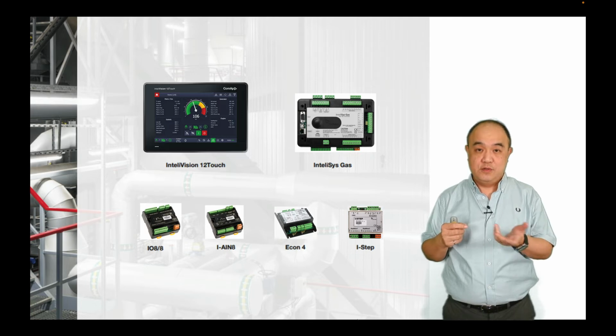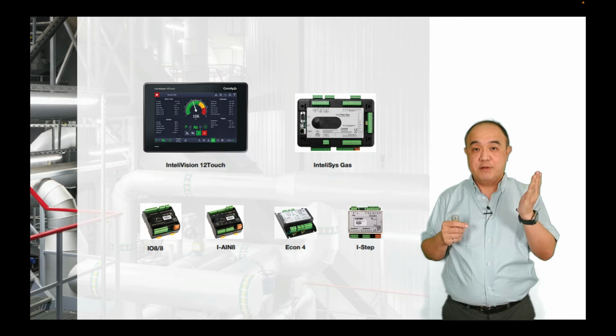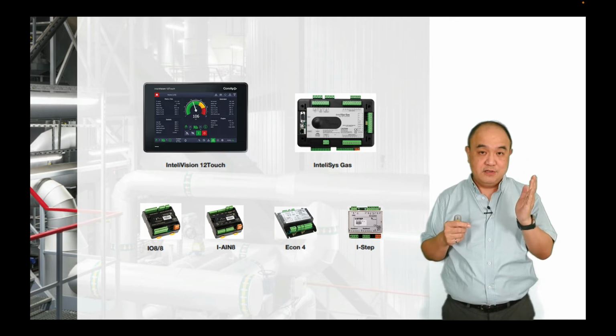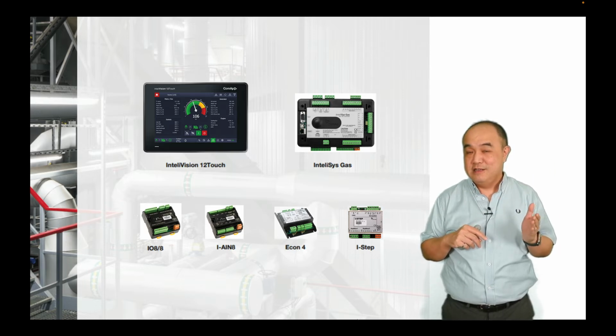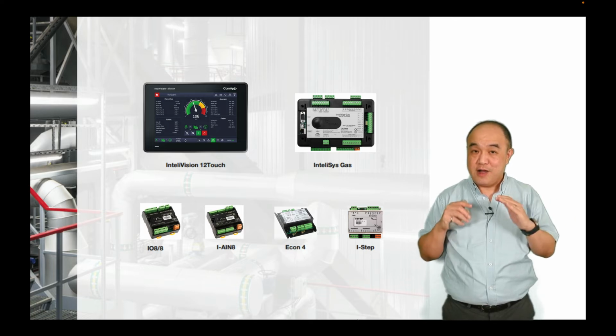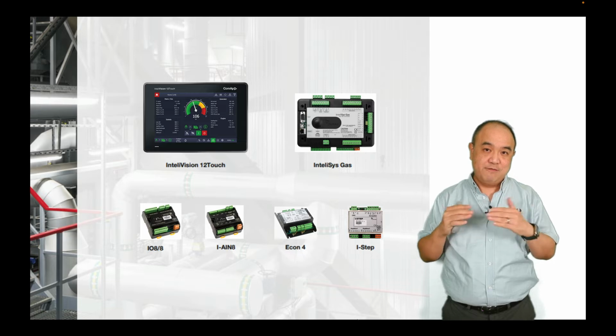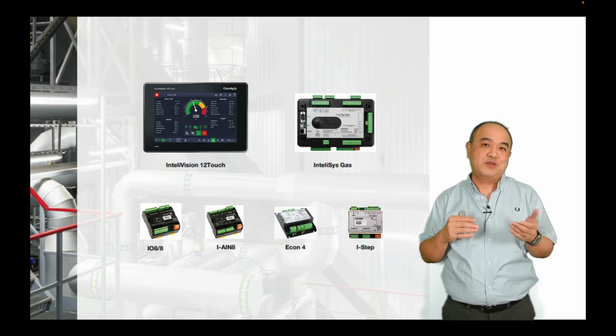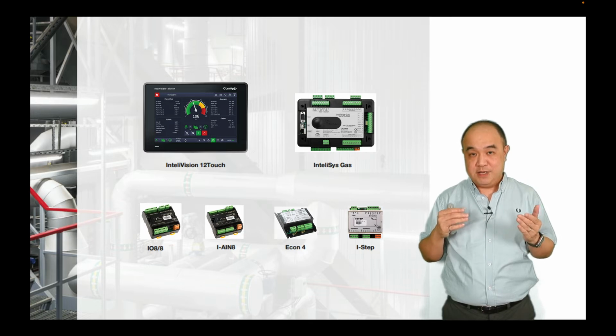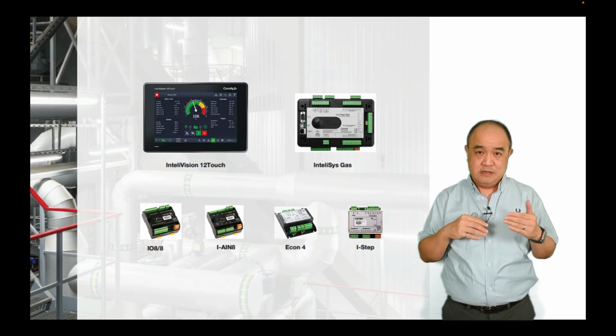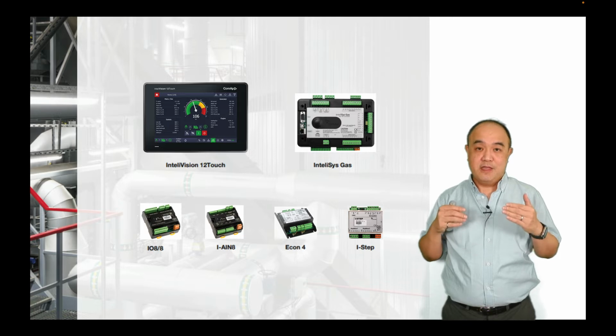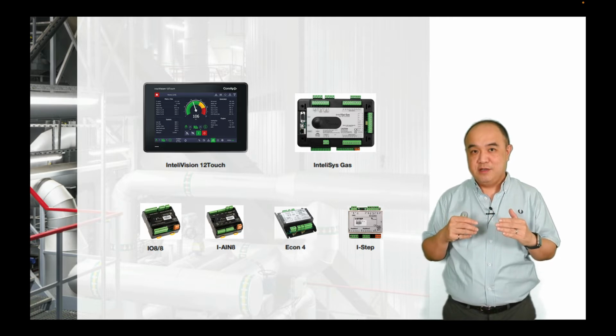For instance, if you use a digital speed control, inside the InteliSys controller for various speed controls you can read the throttle flap feedback, so you know where your throttle flap is. Sometimes in a gas engine, if you have issues with the throttle fully open but not taking much load, you see right away there might be a problem. For us in the InteliSys Gas to read this, and for you to determine what to do about it, is quite easy. If you use a traditional PLC, you'd have to write all the drivers to talk to the speed controls yourself, which could be a lot more work. Everything built into the InteliSys Gas for CHP, that's ComAp's benefit.